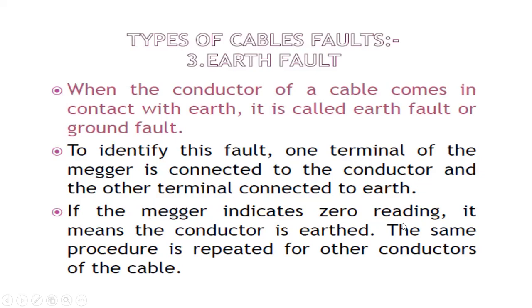If the Megger indicates the zero reading, it means the conductor is earthed. The same procedure is repeated for all other conductors of the cable.